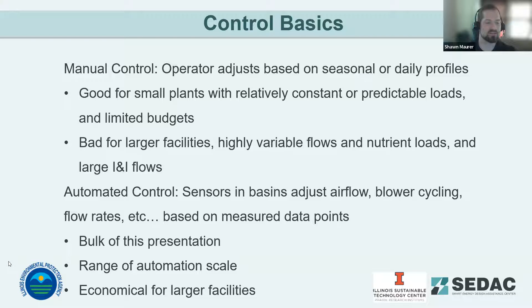Basic things to know are the variables that you're controlling, and how the control system is going to interact. So you're going to have a control variable. Most people are familiar with DO, which is usually a control variable for a lot of activated sludge systems. We'll dig into more details on different control variables here in a minute. Then you'll have a set point reference variable. So this is your DO setting in your SCADA system that you're trying to target. Or it could be an ammonia setting, could be a flow rate target, depending on your control system.